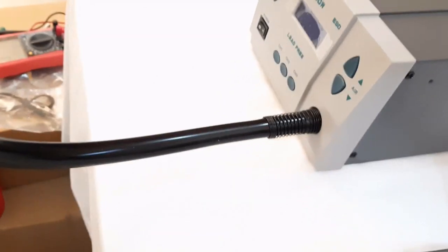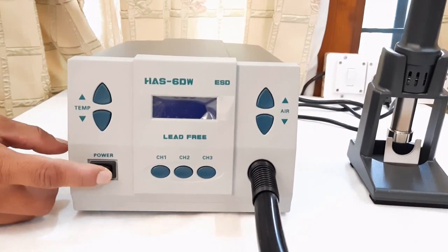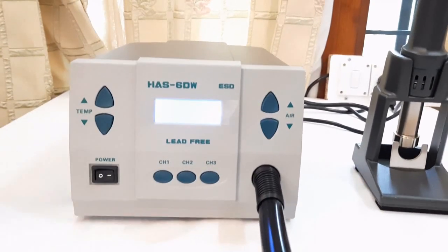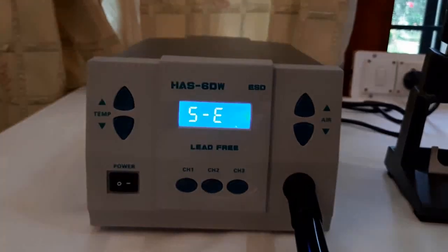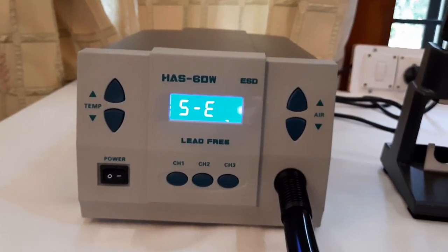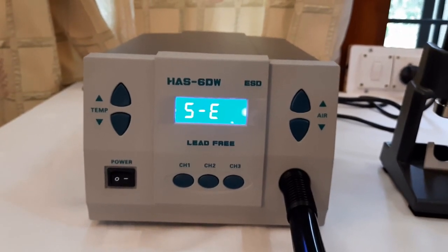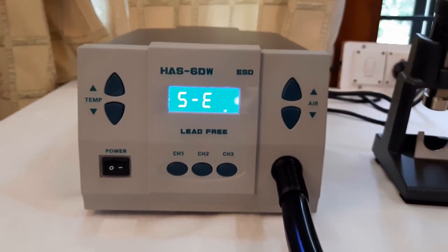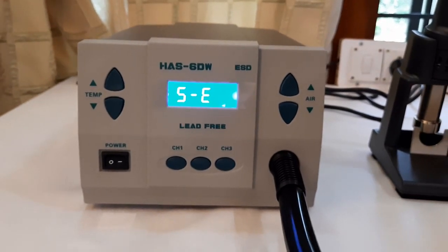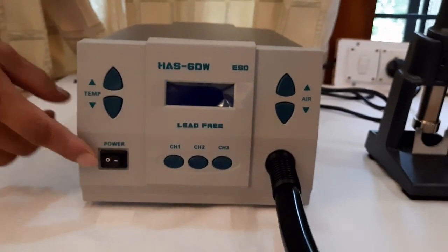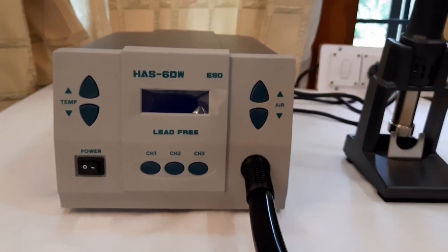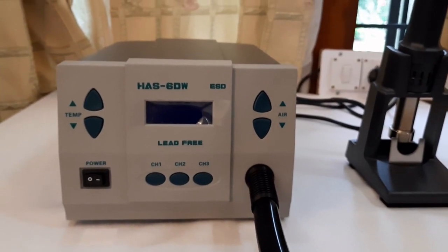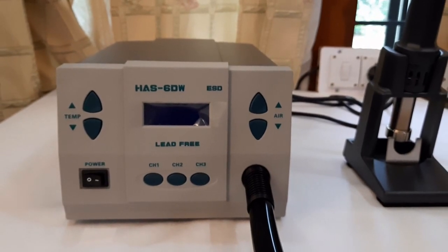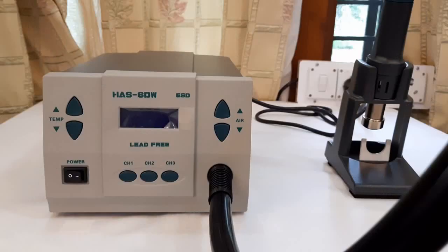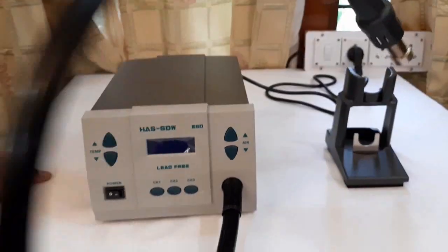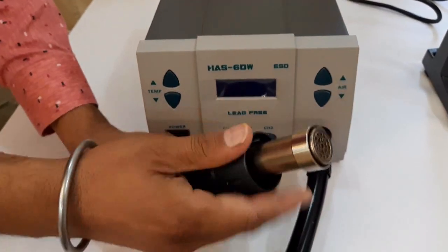And next, one more error we can see when switching on the unit, the SE will be flashing on the display. It means either the heating element or the sensor is faulty. As heating element and sensor are embedded in one enclosure, so we need to replace the whole enclosure if it is found faulty. So let's proceed and check the continuity of heating element and sensor with the help of a multimeter. First we need to take off this soldering iron. Sorry, yeah. Let us check this hot air iron.